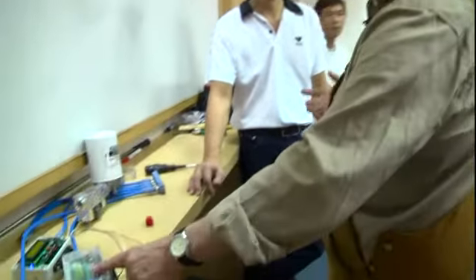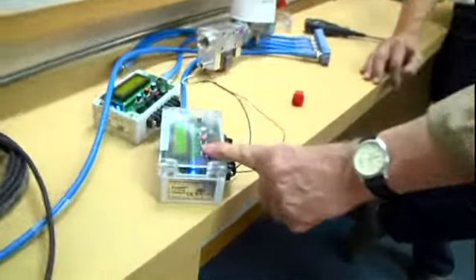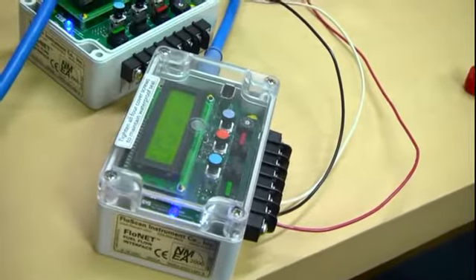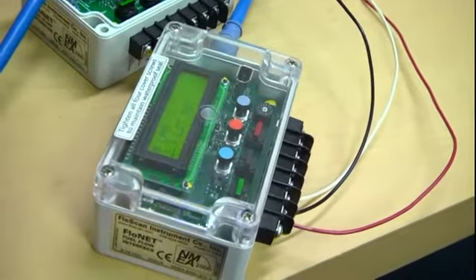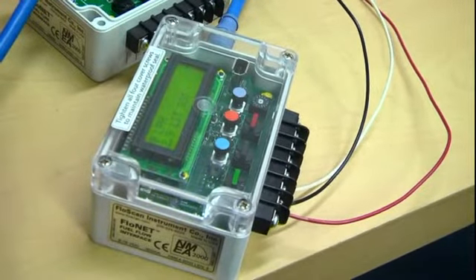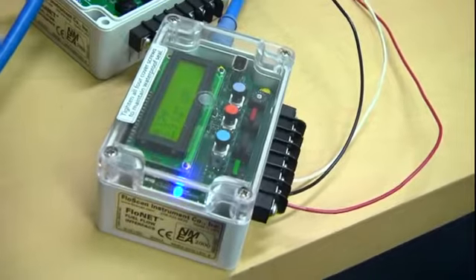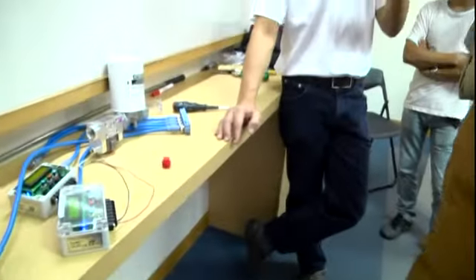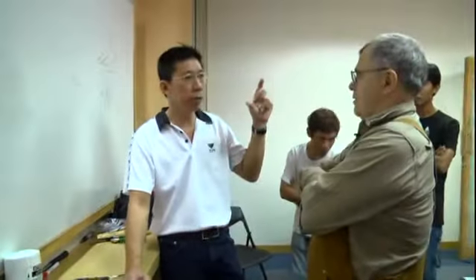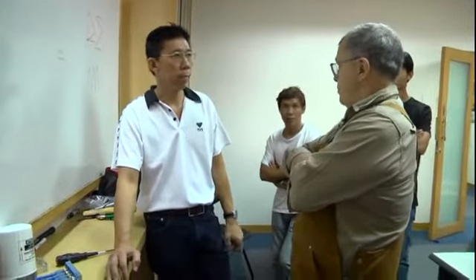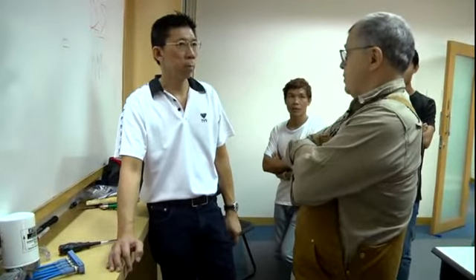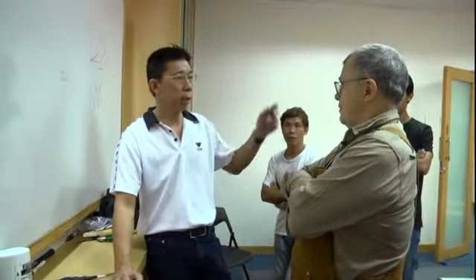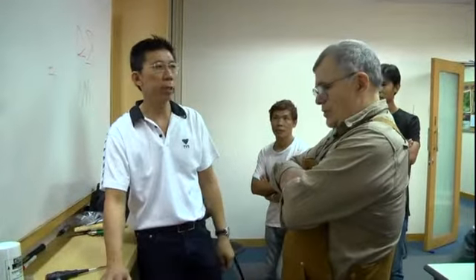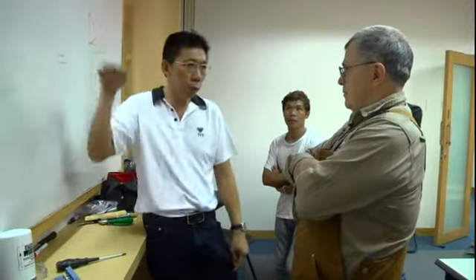If the FloScan totalizer says 10,001 liters, then it's accurate, if it's within a couple of percent of what was actually used. They have to monitor it for a couple of hours, let's say 1 hour, and calculate how much fuel they use. Well, do they have the ability to sound the tanks and know exactly how much fuel they used? I think they have sight gauges. Okay, sight gauges. Maybe you can go through that with us.